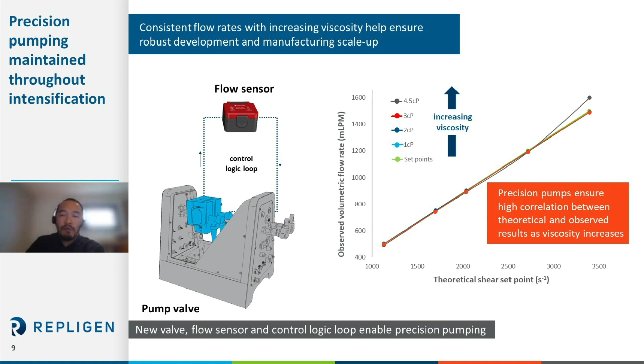To the left, it's a nice schematic to show the newly engineered supporting hardware and control loop, the primary flow sensor and internal valving that are connected by a sophisticated control logic feedback loop. So, this controller really gives the confidence of accurate flow rates and the scale up that's really based on that flow rate. Now, like I said, I'm going to talk more about pressure monitoring. This is a really important data point. We call this permeate pressure, P3, and this enables real-time filter status or fouling monitoring.